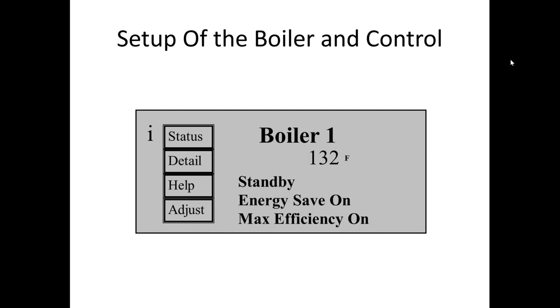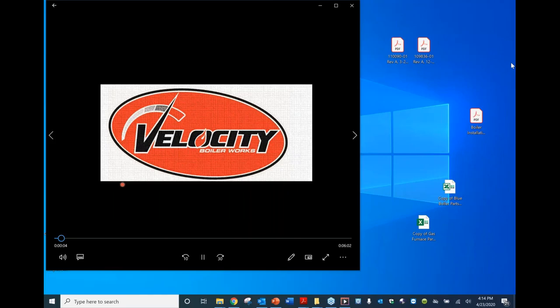In today's video, we are going to cover adjusting the central heating set point in the Velocity Boiler Works condensing line. When the boiler is first energized, we will be greeted by the boiler's home screen. The home screen is going to say boiler or combi at the top, air and supply temperature, firing rate, and the heating demand, whether it's responding to a call for central heat or domestic hot water. Energy save on is going to let us know that the outdoor sensor is hooked up and it's looking for it. Max efficiency on will come and go. That will only be present when the return water temperature is under 130 degrees. So to adjust the central heating set points, we're going to press adjust.